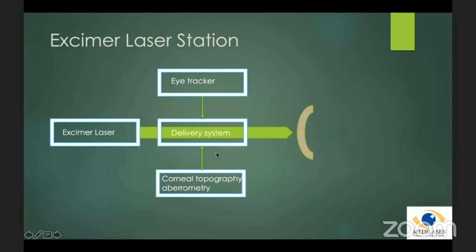So your machine not only has the laser cavity, but there's an optical delivery system after that. That is like a series of prisms and mirrors that homogenizes and equalizes the energy of your laser beam and also reshapes it to your desired configuration. And this delivery system is then coupled with a surgical microscope. There's also a suction system available to pump out the effluent that is generated.